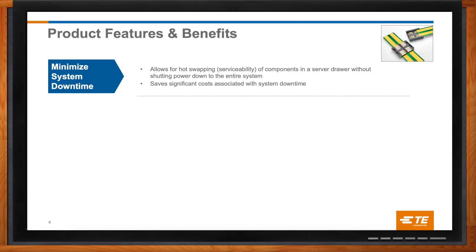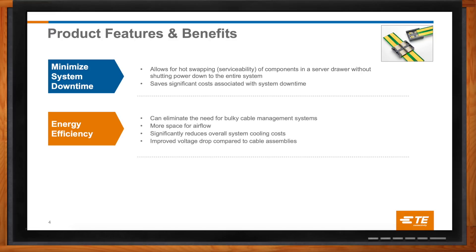This lets you have power on the sliding part with only signal cables coming in. There is also an energy efficiency benefit because longer cables have a larger voltage drop, and your power path goes through that entire cable length whether the drawer is extended or closed. With sliding power, when the drawer is closed — its normal operating state — it's a very short electrical path. With a lower voltage drop, that means more energy efficiency. Very large operators are hugely concerned with power: when you're talking about tens of thousands or hundreds of thousands of devices in a data center, any tiny bit of power savings is amplified hugely.